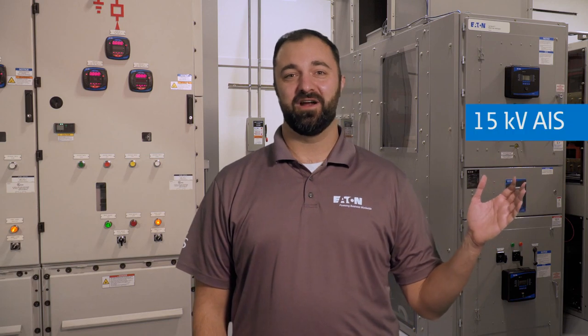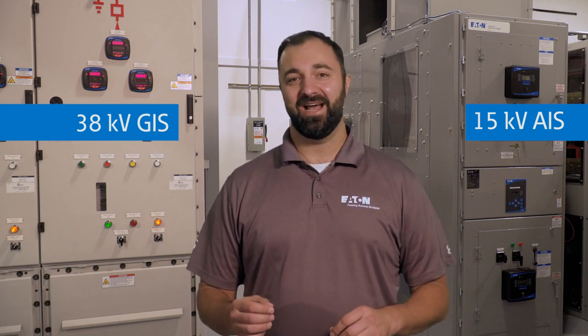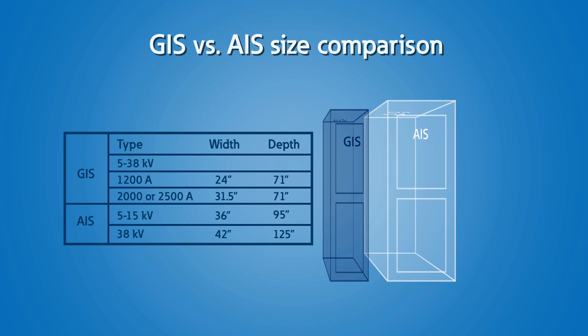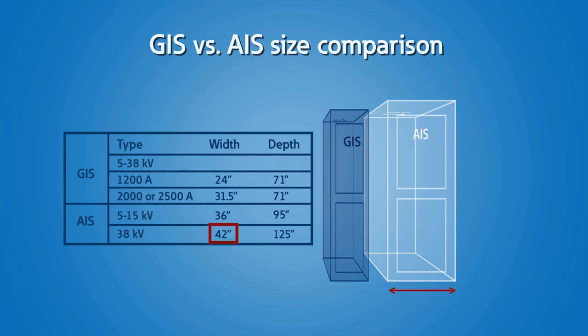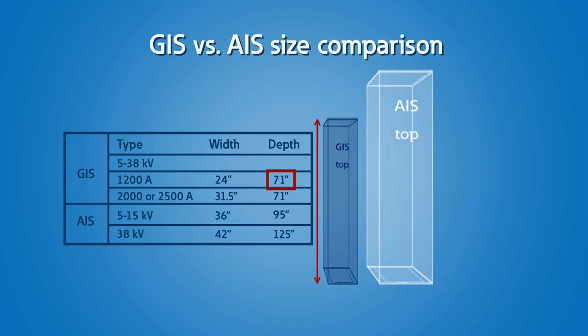Looking to my left, you will see a lineup of air-insulated switchgear, and to my right, gas-insulated switchgear. One major difference between AIS and GIS is footprint. For the 5–38,000-volt GIS structure shown, the 1,200-amp GIS structure is roughly 24 inches wide, and the 2,000 or 2,500-amp structure is roughly 31.5 inches wide. The 5–15 kV AIS switchgear here has a common width of 36 inches for all bus ratings. AIS switchgear at 38 kV is typically 42 inches wide. Comparing depth, GIS is roughly 71 inches deep for all voltage classes, but AIS gear is 95-plus inches deep depending on the voltage class and rear compartment configurations.